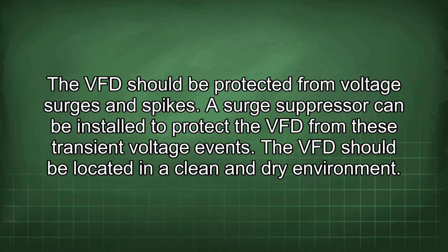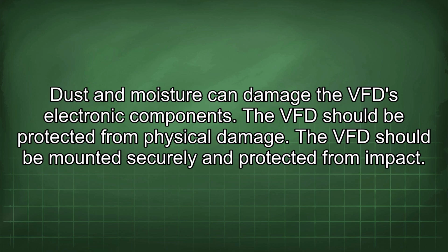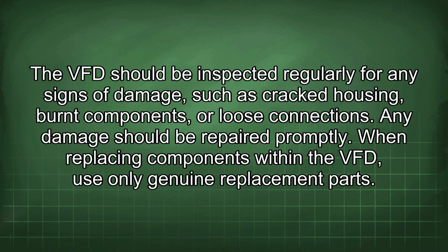The VFD should be protected from voltage surges and spikes. A surge suppressor can be installed to protect the VFD from these transient voltage events. The VFD should be located in a clean and dry environment. Dust and moisture can damage the VFD electronic components. The VFD should be protected from physical damage. The VFD should be mounted securely and protected from impact. The VFD should be inspected regularly for any signs of damage, such as cracked housing, burnt components, or loose connections. Any damage should be repaired promptly.